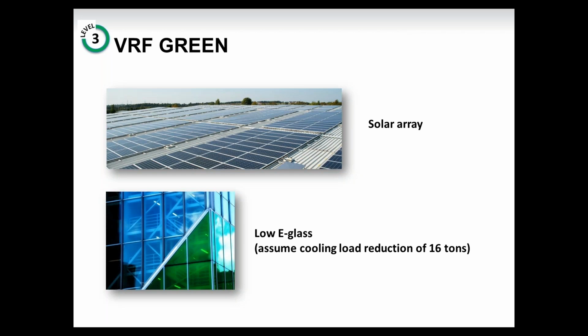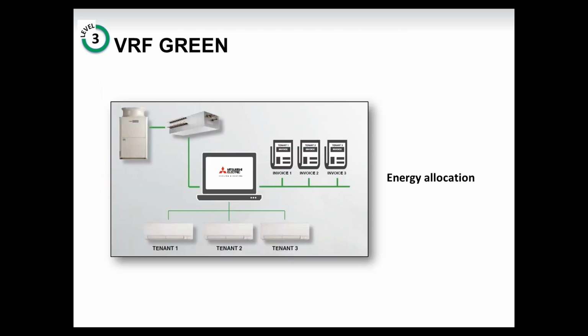Low E glass will reduce the cooling load by 16 tons. Also, it does add some cost on there. Rule of thumb for glass is $45 per square foot with a 10% add for low E glass. We based our pricing of the glass on 3 bands of 5-foot tall windows around the entire perimeter at that $5 per square foot premium over standard windows. Also in this solution, energy allocation rather than blindly lumping energy cost into the CAM rates is a given, and our city multi-control network provides that option as part of the original package.